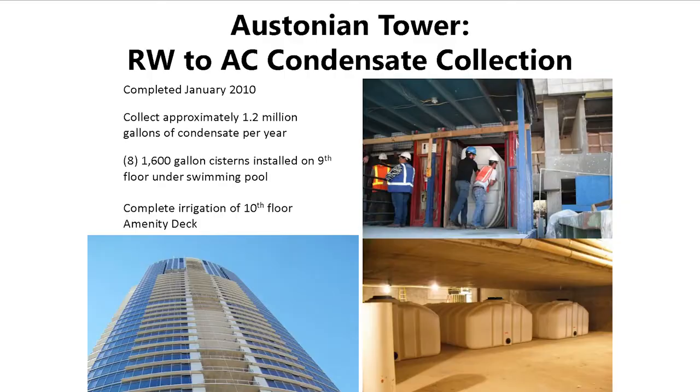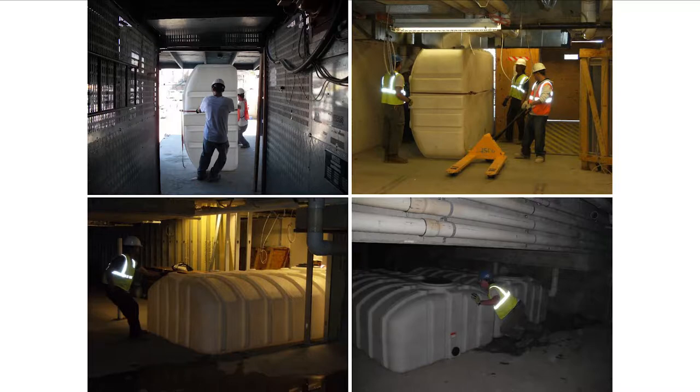The Austonian Tower — everyone knows it. I was brought into this project looking at collecting rainwater from the 10th floor Amenity Deck. The building goes up 10 floors and then into the residential tower, collecting rainwater falling on that deck. Through the design process we found a much bigger resource in the AC condensate — calculating an average of about 1.2 million gallons of AC condensate per year, versus about 300,000 gallons from a typical 30-inch annual rainfall collection from the 10th floor Amenity Deck.